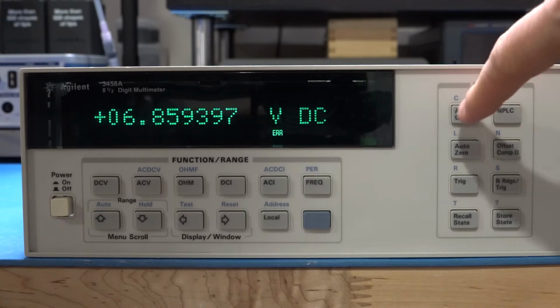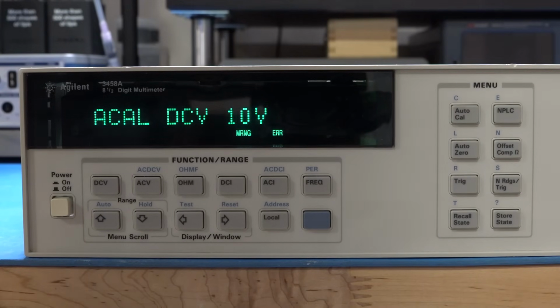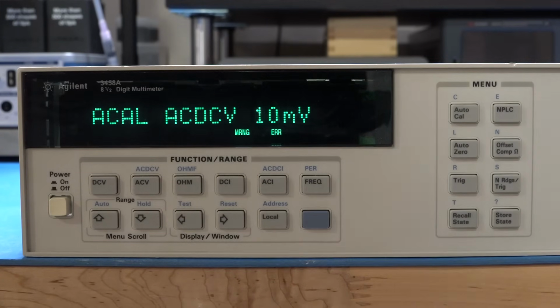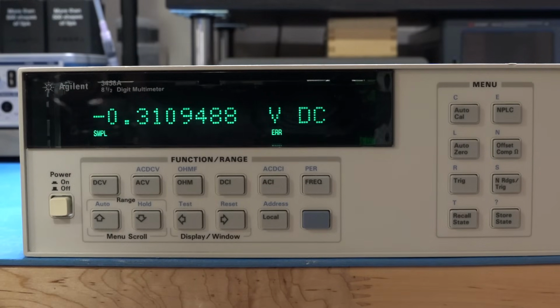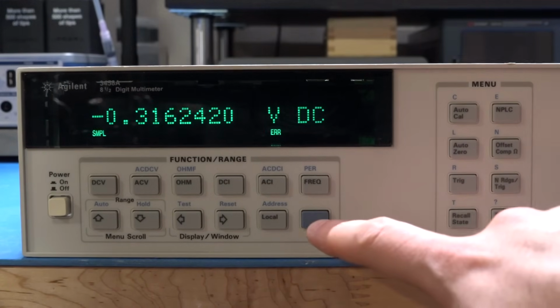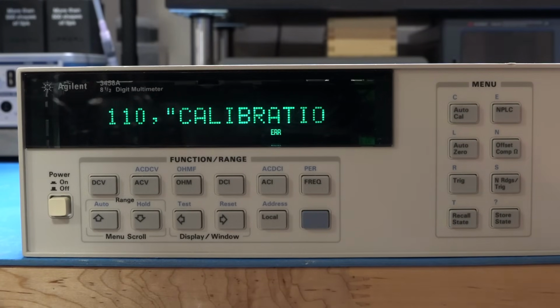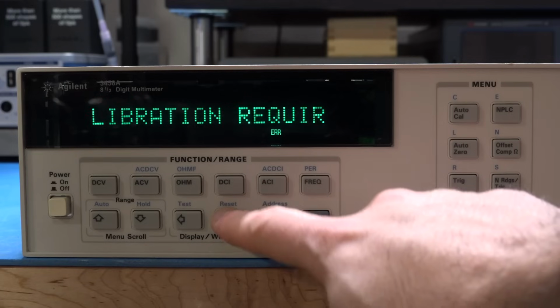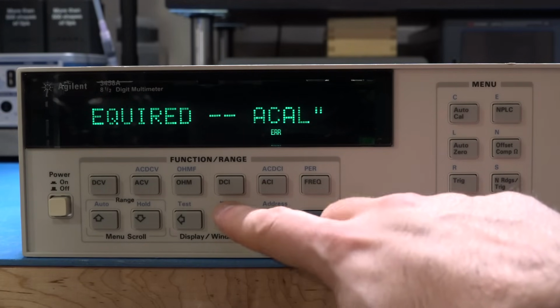Okay, we run ACAL again, same as before, and let's see if it passes through the resistance now. And check it out, it passed the ohms self-calibration, it passed some DCI current calibration, so it's looking good. It's doing something at the end in the AC mode, and let's see if it finishes. Well, it finished, didn't give any more error. There's this error still here, but I think that's the non-volatile memory. I think it says, yeah, it says calibration required, which I just did, so probably have to restart it.